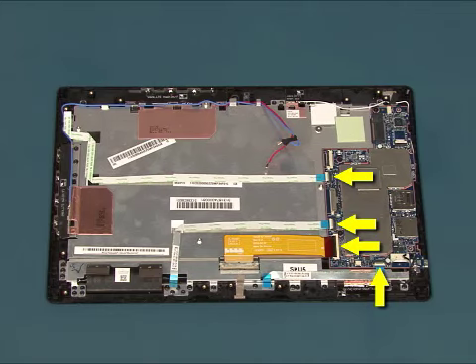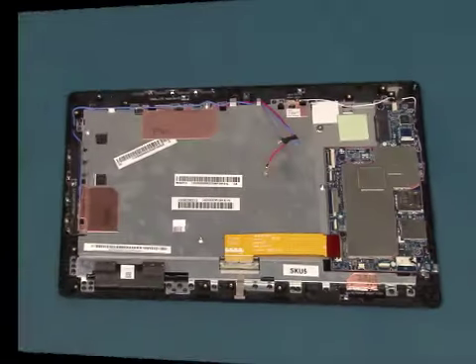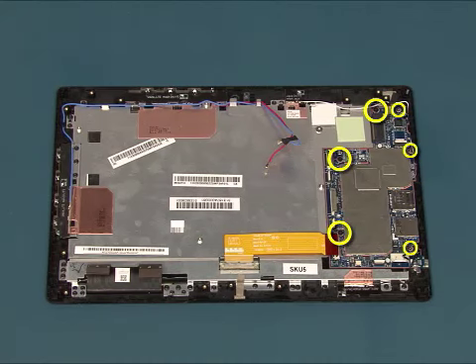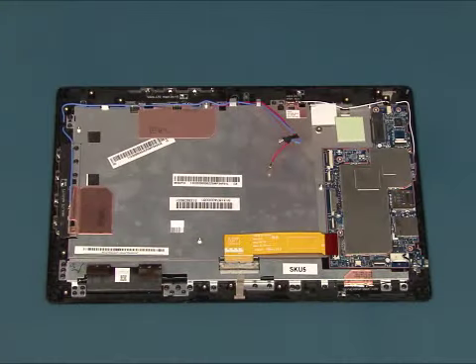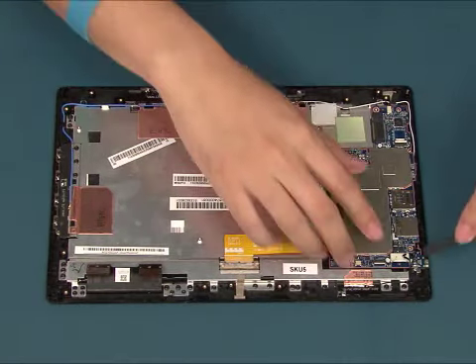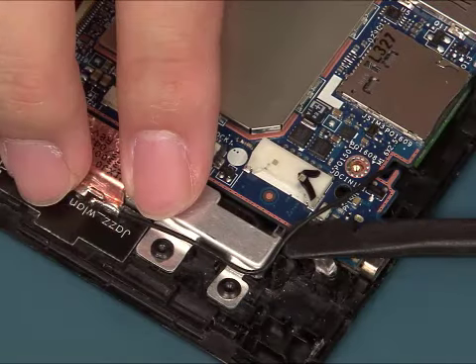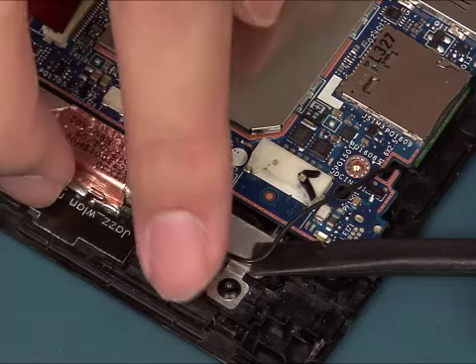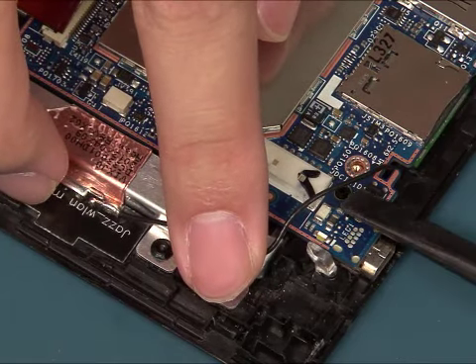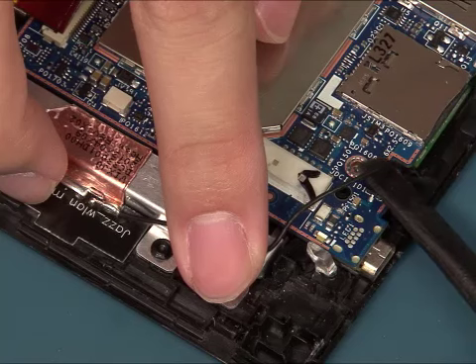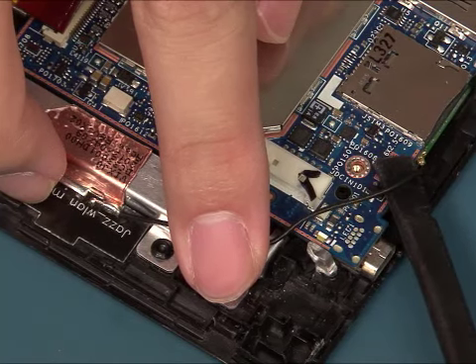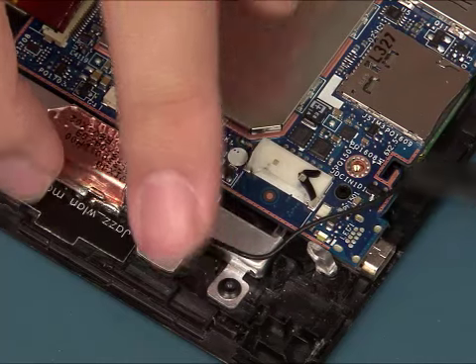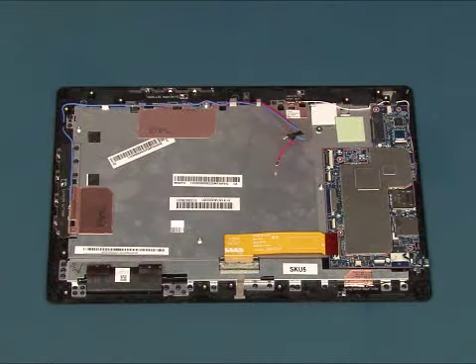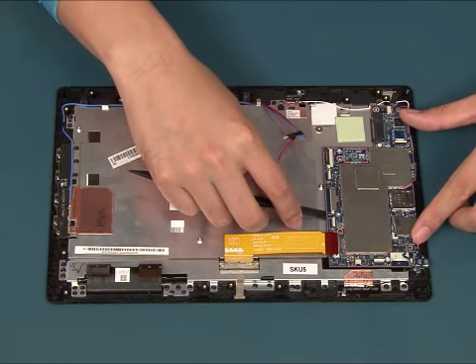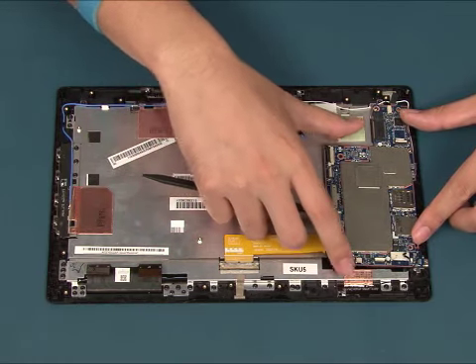Remove all remaining cables from the system board. Remove the 6 screws that secure the system board to the frame. Release the wireless antenna cable from the guide to make space for the removal. With a probe, release the adhesive backing. Lift the system board up.